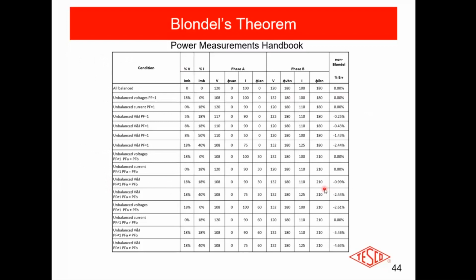In this power measurements handbook we put together, you can see that sometimes if you have a non-Blondel setup, you can get perfectly good information. Power factors of 1, slightly unbalanced voltage or current in this particular case. But when you start getting an unbalanced current and voltage, which you typically have, I don't know too many systems that have perfectly balanced in either of those, even with a power factor of 1, you can start going off. You can start going much further off. If you look down here, 2.4, 2.6, 3.4, 4.63. You can start getting very unbalanced loads, very unbalanced voltages in here, power factors that are starting to go to heck in a handbasket, and you start getting, again, even with everything working correctly, you're starting to introduce 3, 4, and 5% errors.